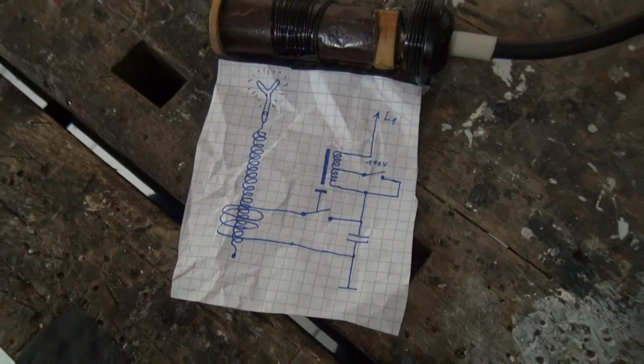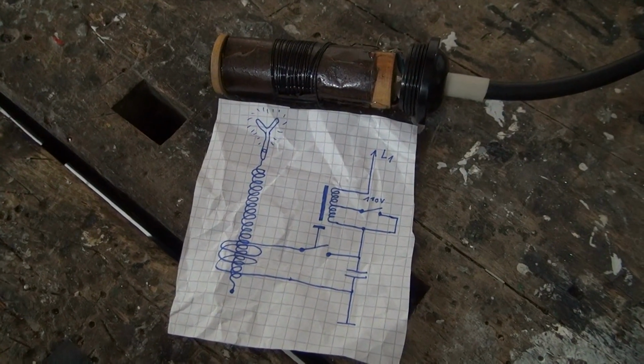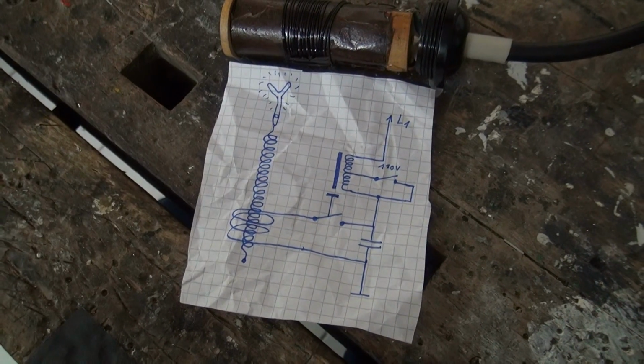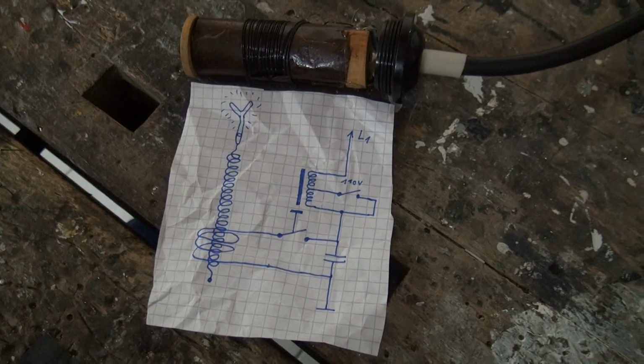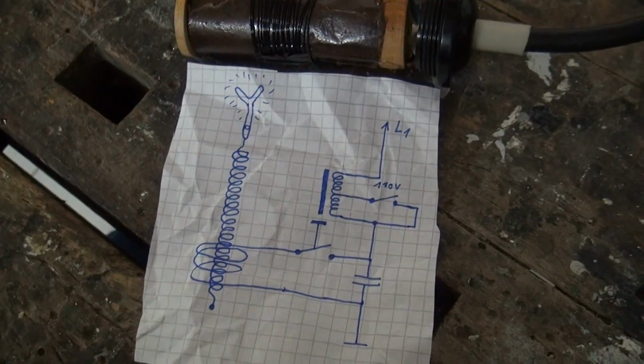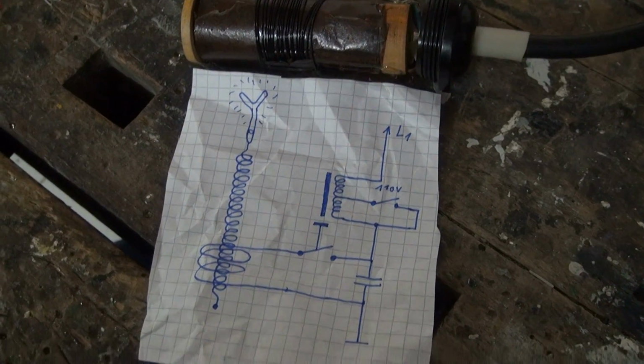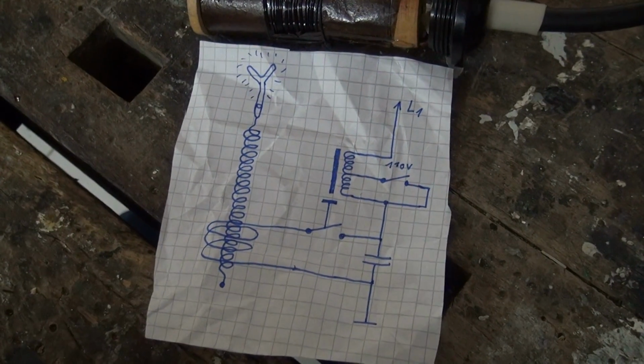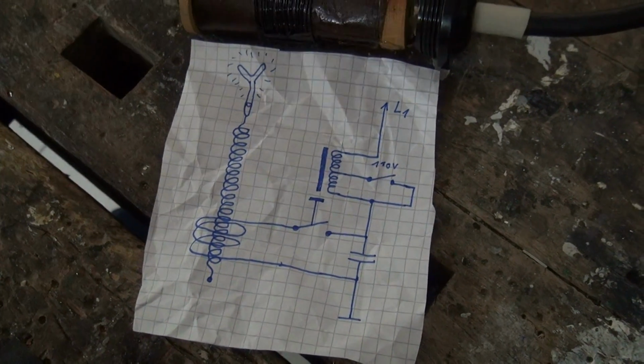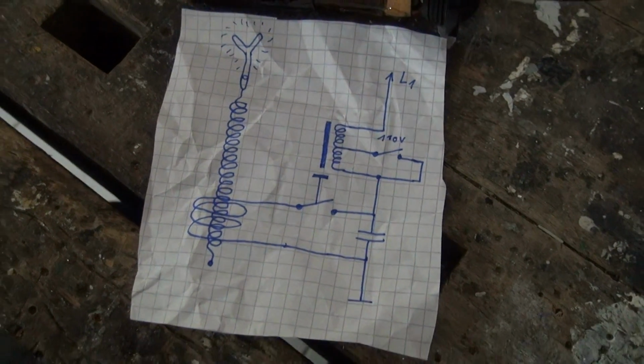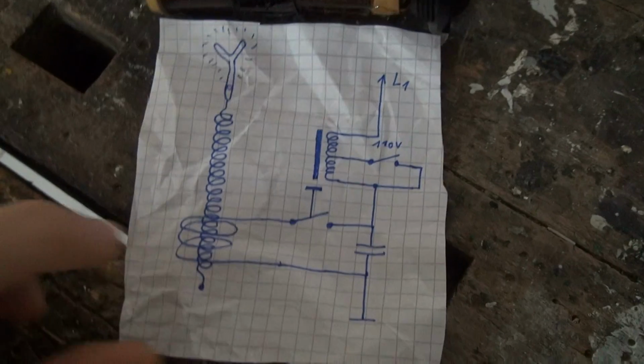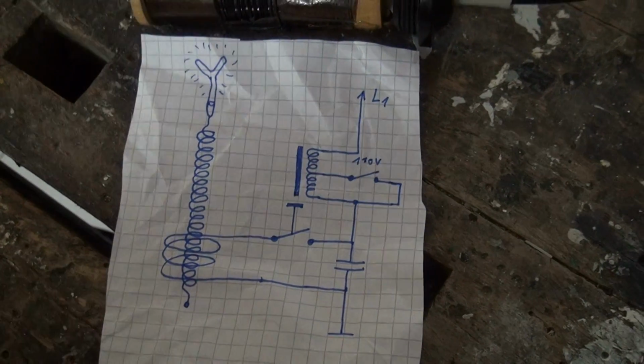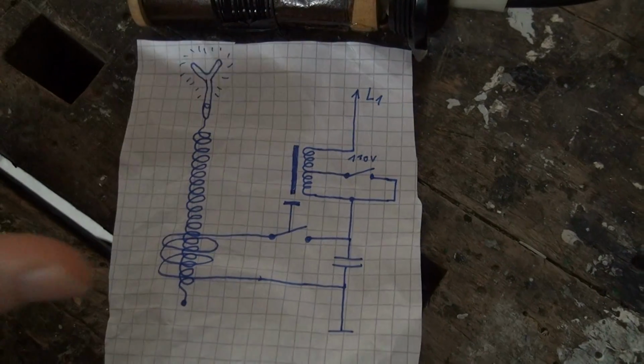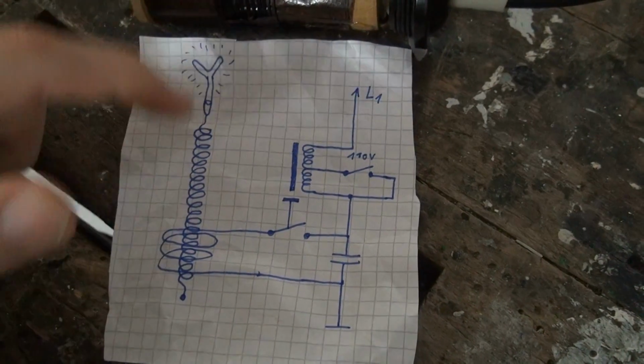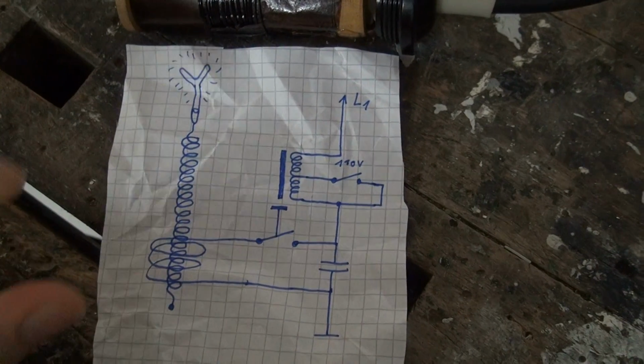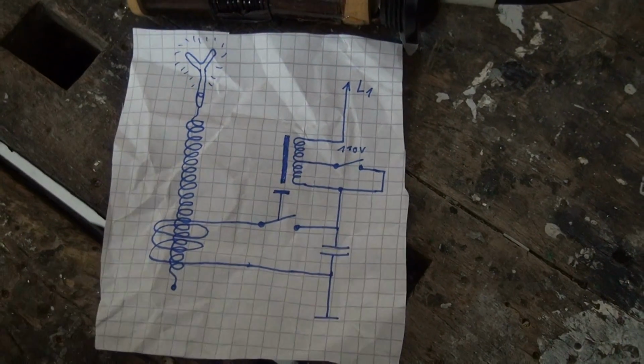So the glass electrodes basically give a little bit of additional safety, because you have a capacitance in series - the glass is a dielectric substance. Even if you touch the glass directly, or there's an arc coming out of the glass, you are still insulated by a capacity. So the other point of the primary coil is not connected to anywhere. So at least in series, this circuit is not connected to the power line at any point in time.